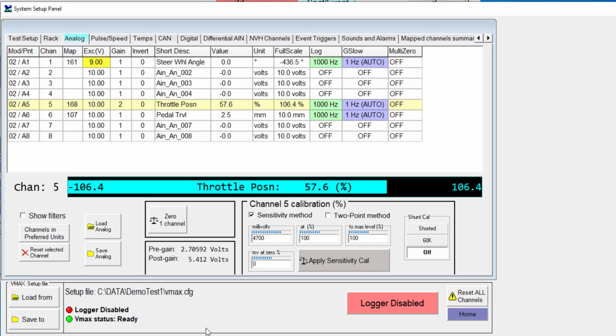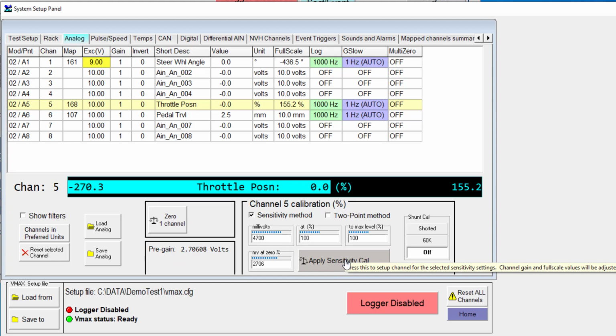So there's two ways that I could handle this. One way would be that I could just zero this channel, and that will still preserve the relationship that I've established here for the slope of that line while forcing it to be 0, so essentially just moving the 0 offset. Or if I just reapply this sensitivity, I could also enter in the value that I'm seeing here in millivolts. So we're seeing essentially about 2,706 millivolts. I hit enter, and you'll notice the apply sensitivity button lights up. Go ahead and push that. Now we can see I'm down to 0. When I step on the pedal, it goes up to 100%. When I release the pedal, it goes down to 0.